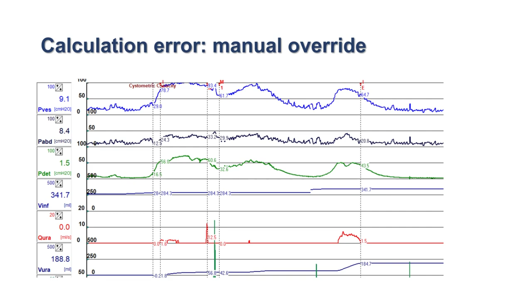This is another situation in which there is a knocking artifact in the Q ura. Unfortunately, the computer did not take it as an artifact, and it measured the Qmax and the PDET Qmax based on the artifact. So in this, we have to be mindful and do it manually. Now this is the normal, and this is the actual where we should be measuring the PDETs and corresponding flows.